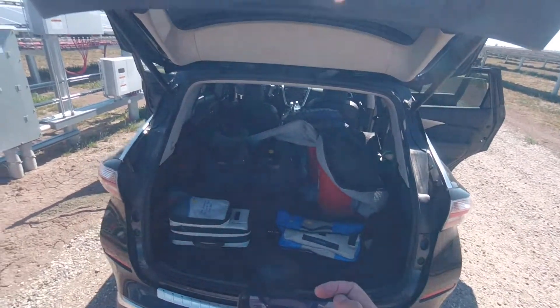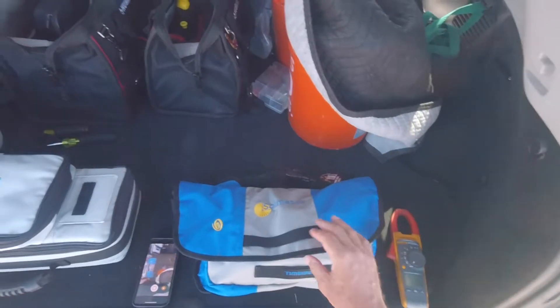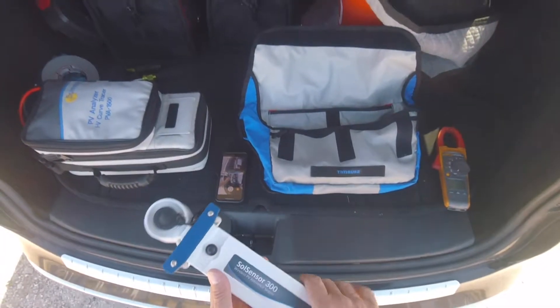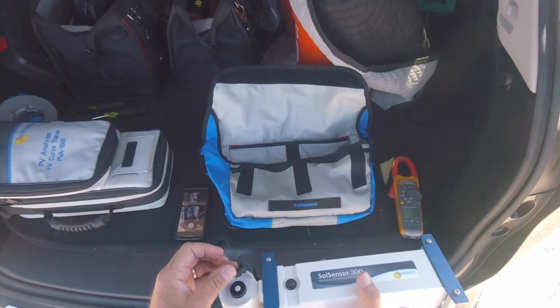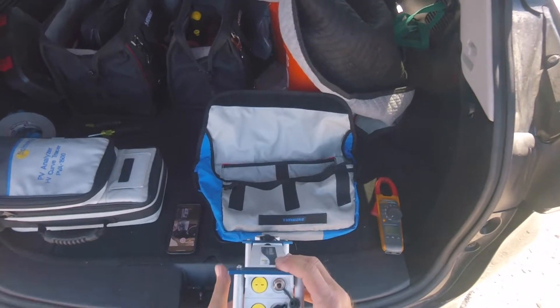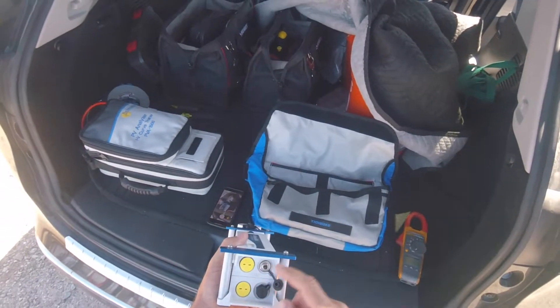Here's just a little walk around. Right here we have two of the components of the IV curve tester. This bag here is the unit that goes on the array — the SolSensor 300 — and it has an irradiance meter, an on/off button, and jacks where we connect the back-of-module temperature sensor. There's T1 and T2 for two channels so we can measure two channels, but we're just going to use one sensor.